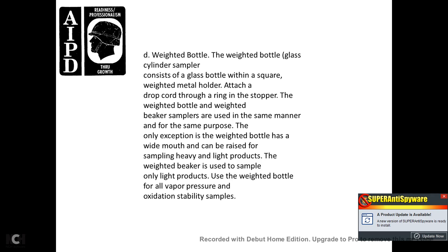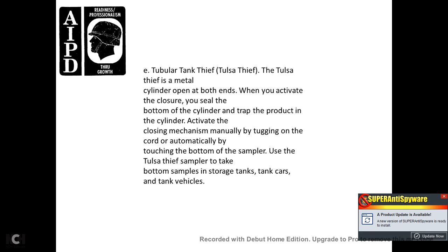Bacon bomb thief (tanker car thief): a nickel-plated brass cylinder tapered at the bottom, fitted with an internal plug vent and plunger valve. The valve opens automatically when the sampler strikes the bottom of the container, and closes automatically when you lift the sample. A trip cord makes it possible to open the cylinder at any level. Use the bacon bomb thief to take bottom samples and samples in storage tanks, tanker cars, and tank vehicles. Tubular tank thief (Tulsa thief): a metal cylinder open at both ends; when you activate the closure, you seal the bottom of the cylinder and trap the product. The closing mechanism is activated manually by tugging the cord or automatically by touching the bottom. Use the Tulsa thief to take bottom samples in storage tanks, tank cars, and tank vehicles.